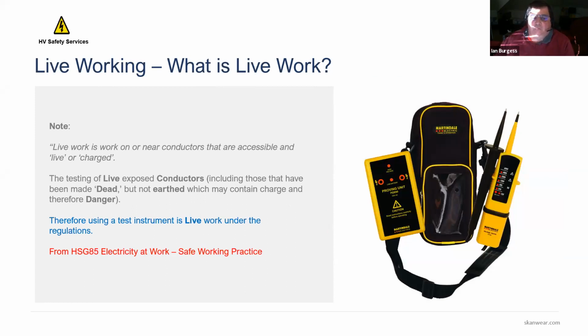So what do we see? What's live work? Most people will probably say, don't do live work. Well, in the UK, it's been decided that testing is considered work. And therefore, when you test to prove dead, you're carrying out work. So you're in this catch-22 situation in some ways. You can't issue a safety document because you can't prove it's dead. And you can't prove it dead because it's work, because you haven't issued a safety document. However, the HSE recognise that you still need to do testing. So there's a caveat within the rules that allows testing to take place, just as well, really.